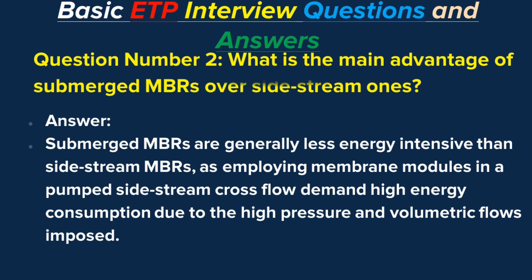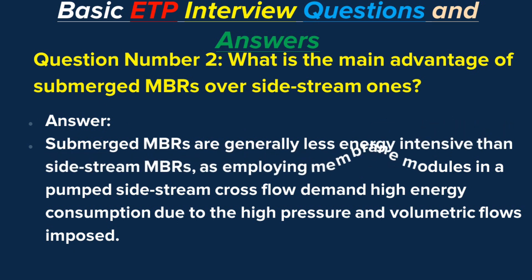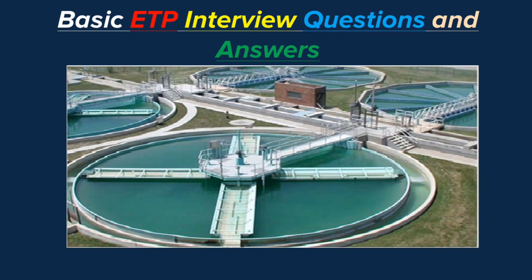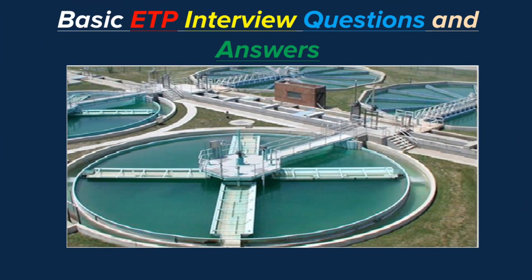Question number 2: What is the main advantage of submerged MBRs over sidestream ones? Answer. Submerged MBRs are generally less energy intensive than sidestream MBRs, as employing membrane modules in a pumped sidestream crossflow demands high energy consumption due to the high pressure and volumetric flows imposed.